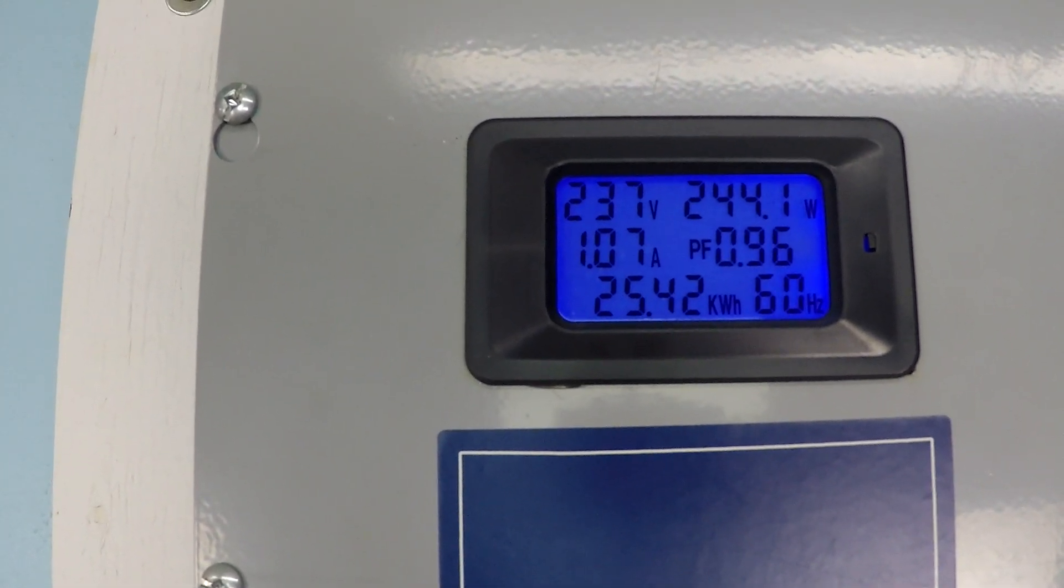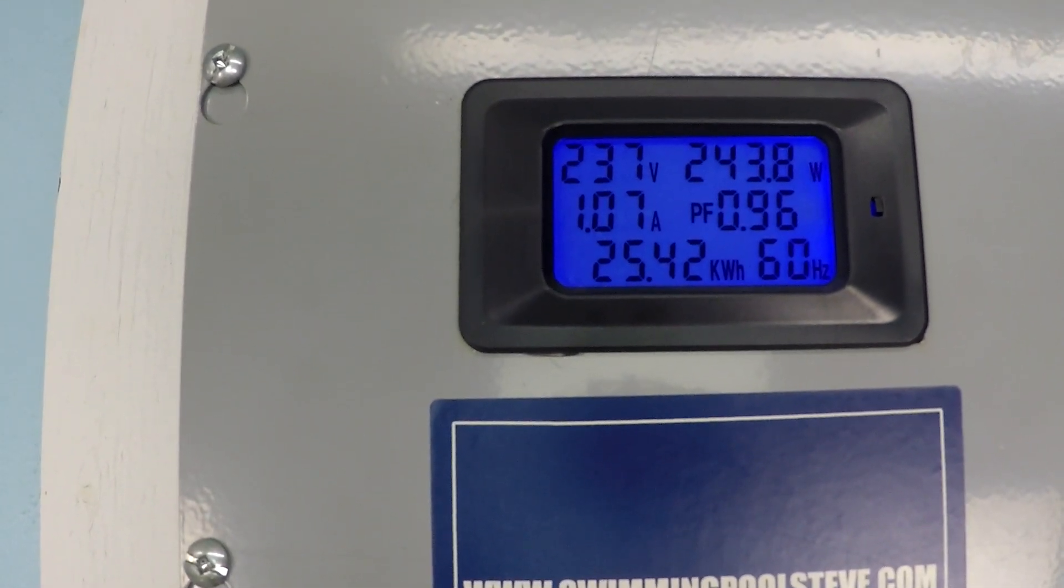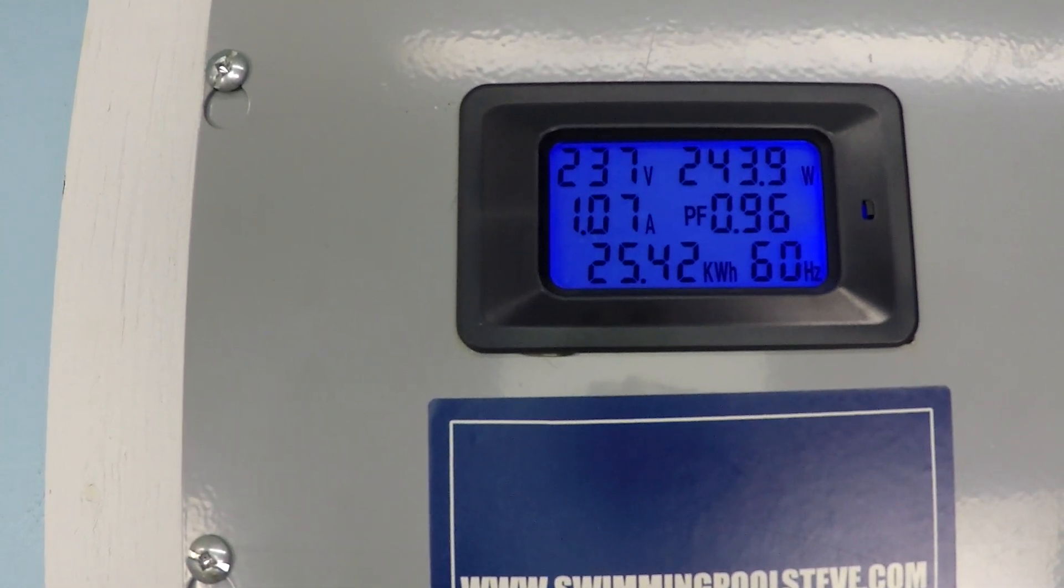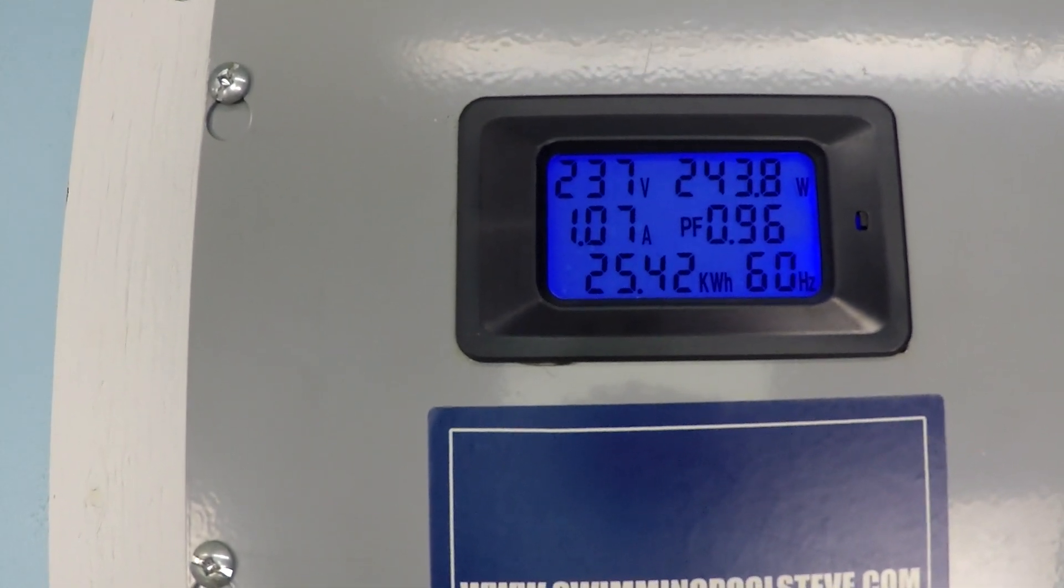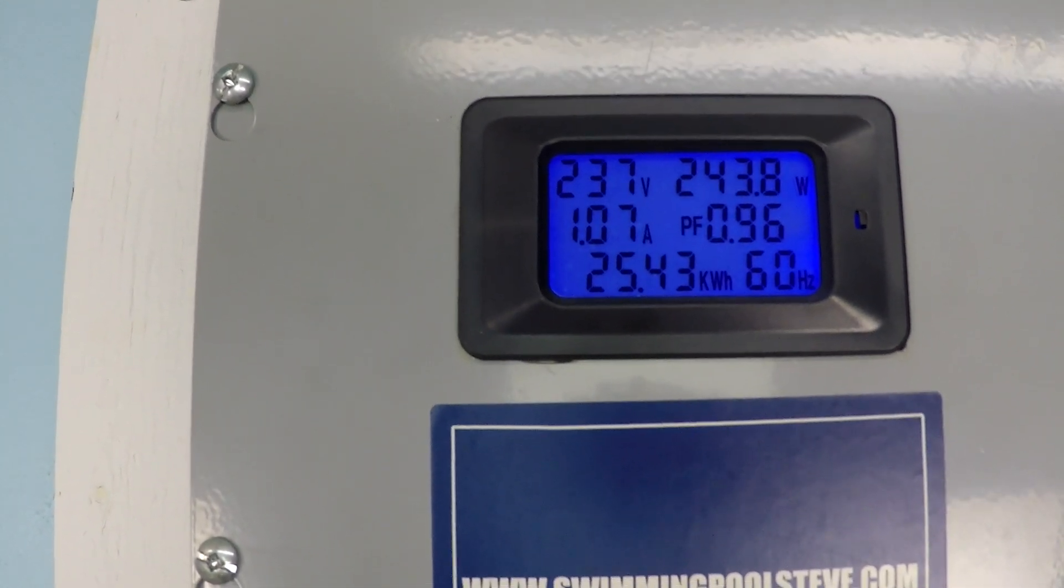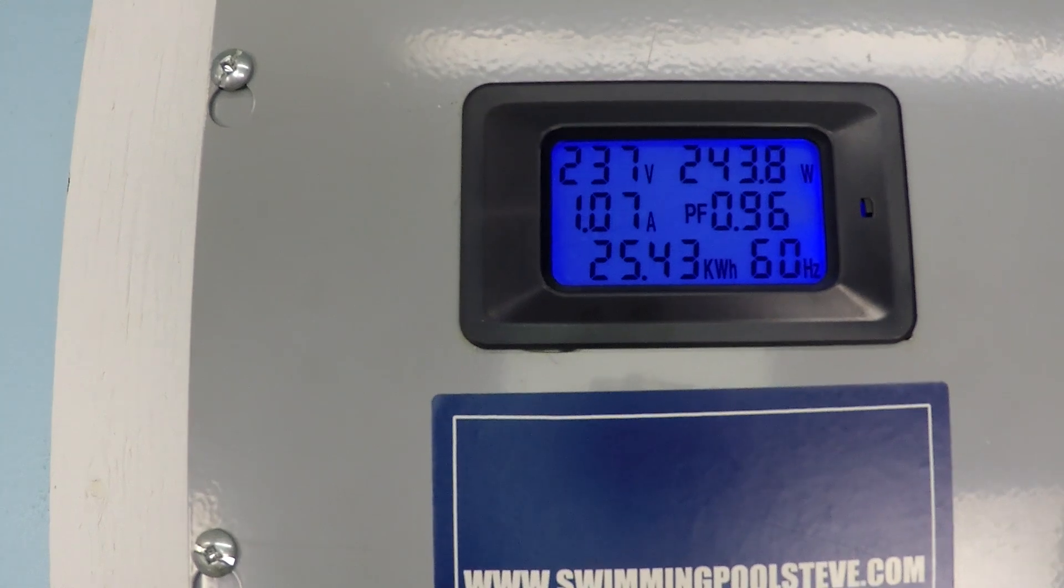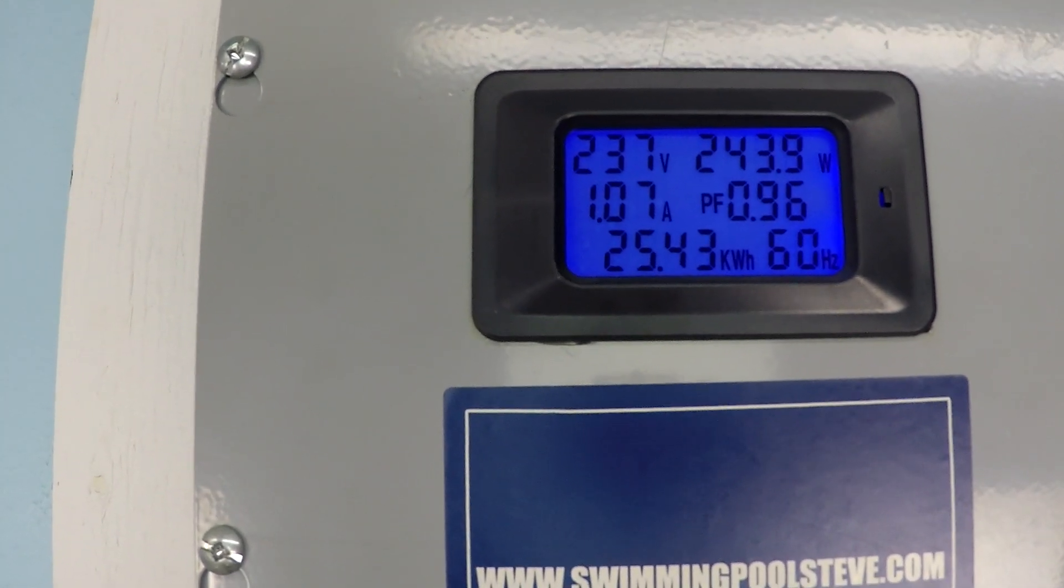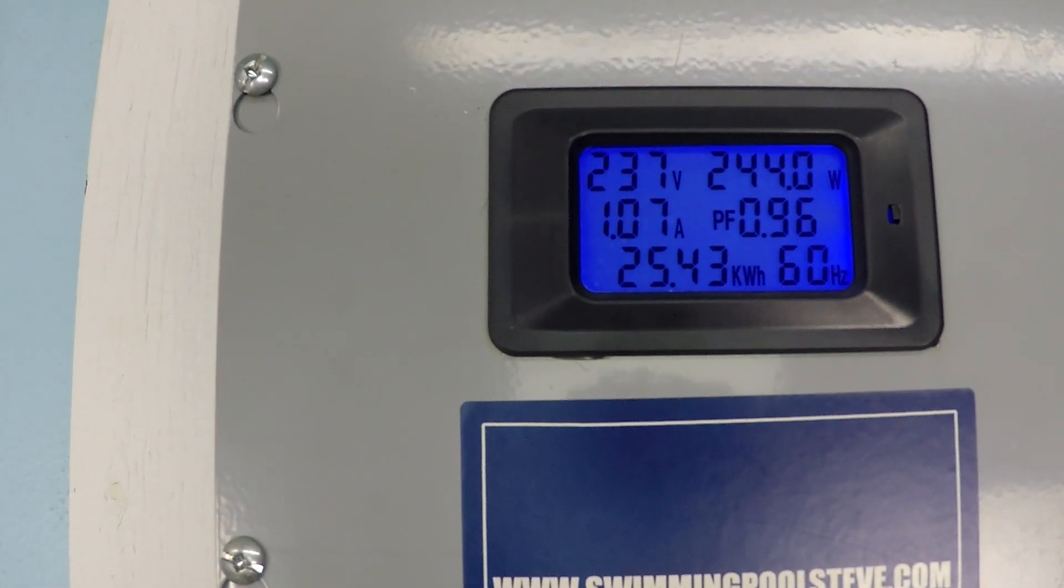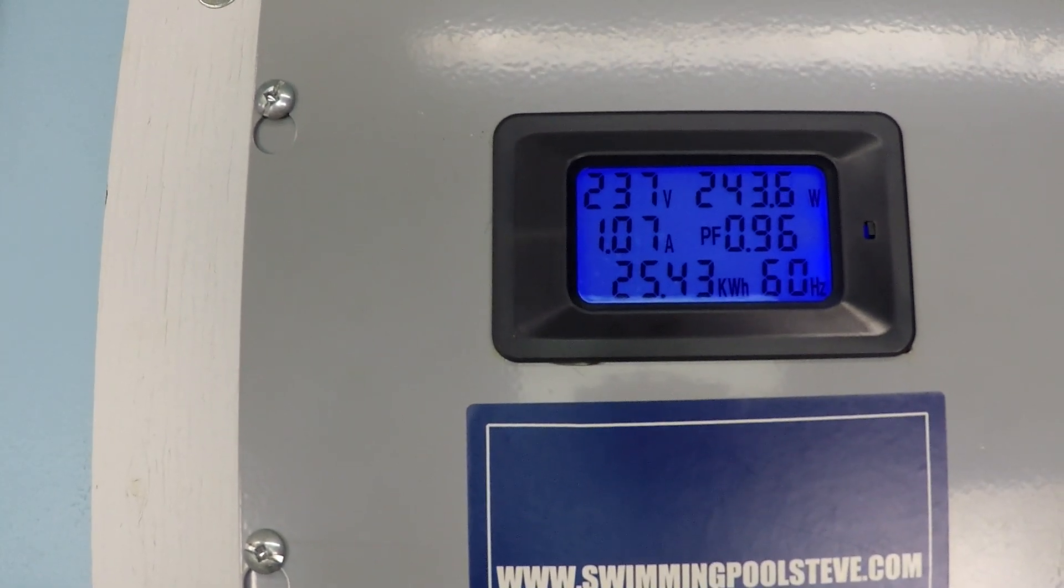244 watts of power consumption is certainly not halfway in terms of power consumption. The top end power consumption is over 1,500 watts for this pump that's running right now. So that really just goes to show you, as you dial down the speed, you really dial up the savings.